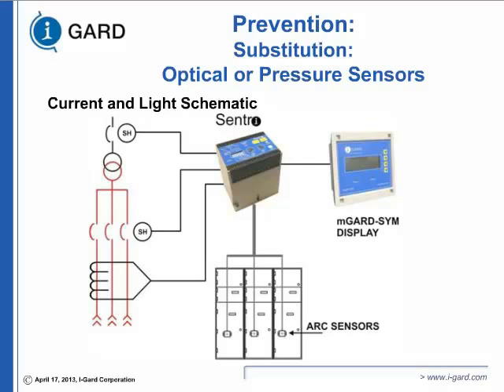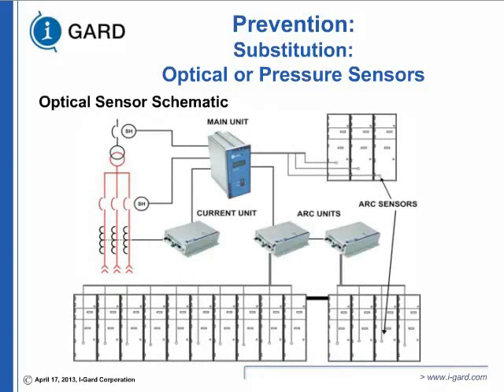That Sentri device you see, that's made by I-Gard, has the optical detection input built in, and then you have a display center. Same thing you see in that layout of optical or pressure sensor. You have a trip unit that can accommodate multiple devices, the current unit input or pressure sensor input. That way you can have an AND gate to prevent false tripping and cut down the incident energy.